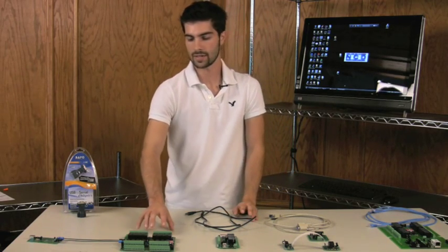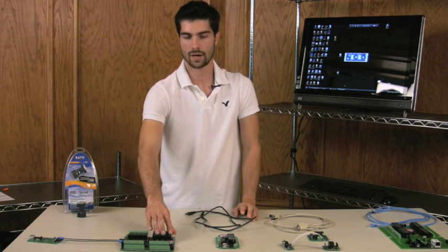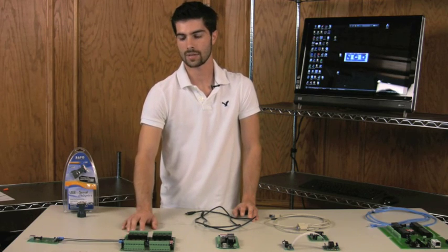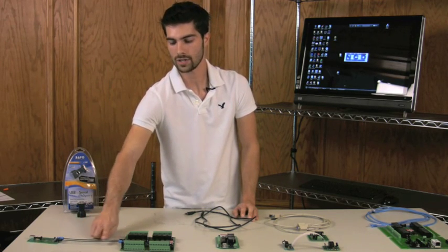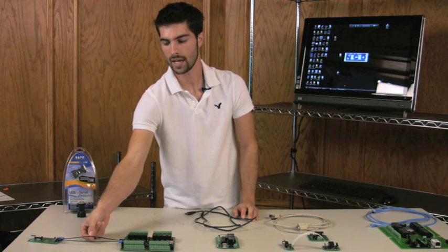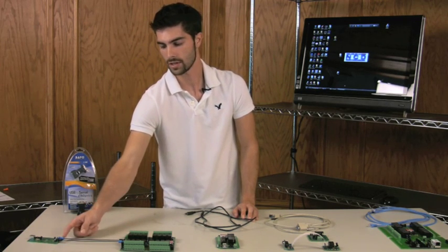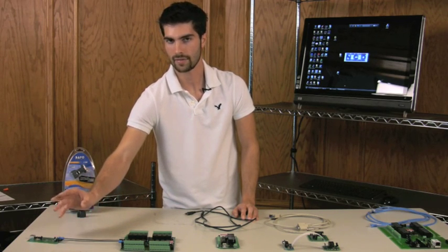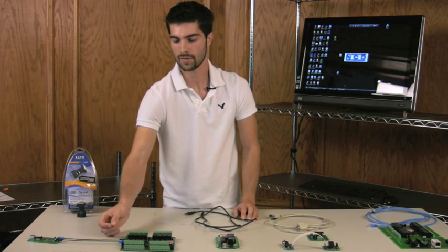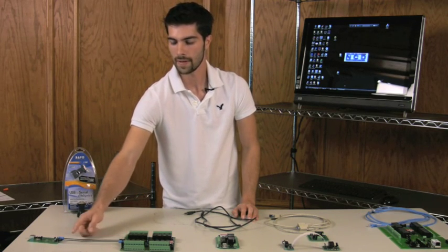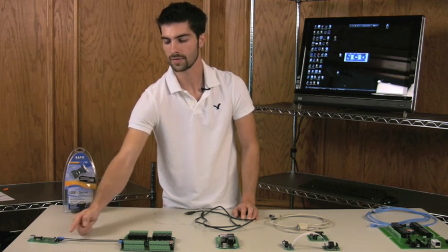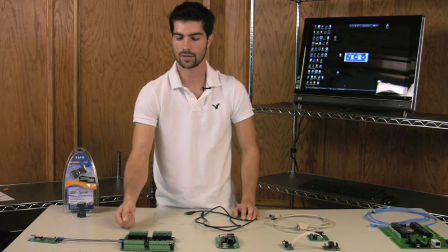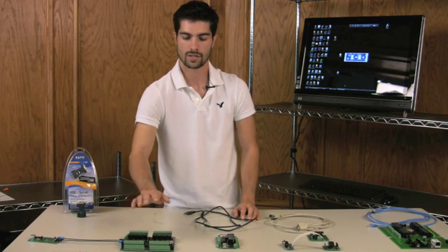The next one is fiber optics. We designed our fiber optic controllers specifically for controlling inductive loads. The reason being, there is no hardwired connection between this and your computer. You have these cables here, but it's not a wired connection. It's a channel through which communication goes. On one end, you have a light that flashes, and then on the other end, you have a receiver that reads those light flashes. So there's no way for EMI to get through this cable. You can make these fiber optic cables up to 24 feet long, and you can control large motors or things of that nature. So that's perfect for that.